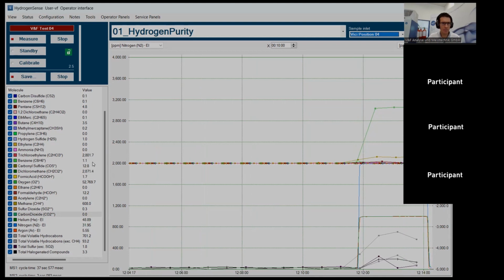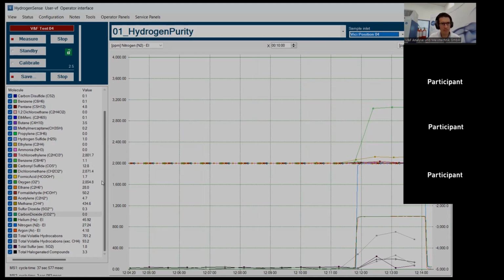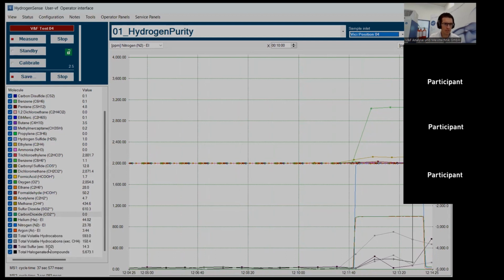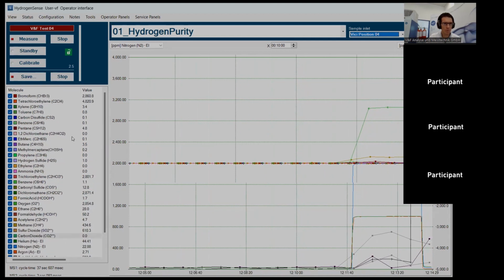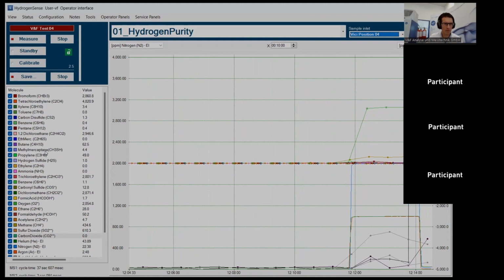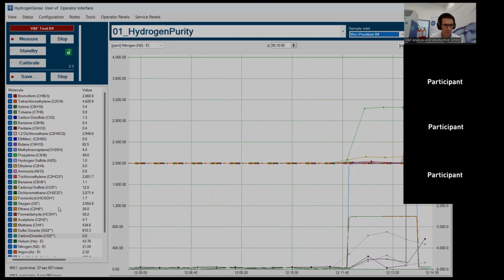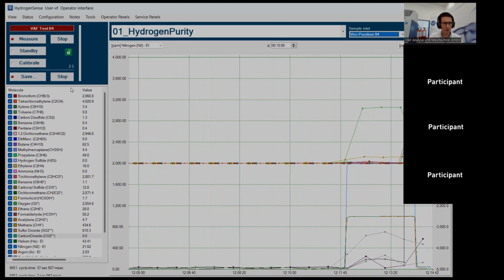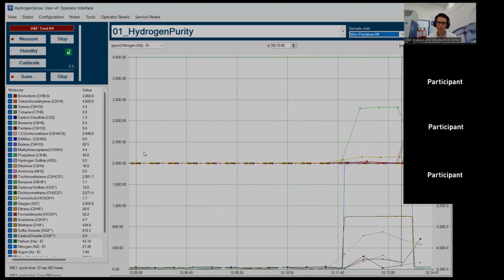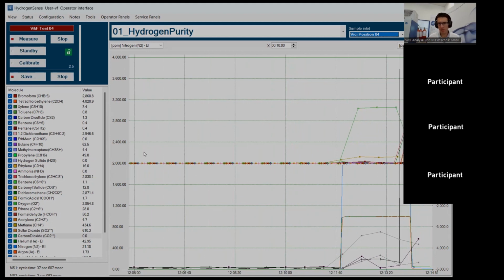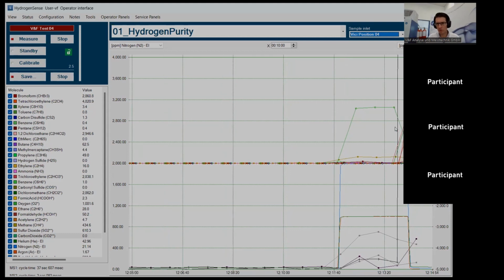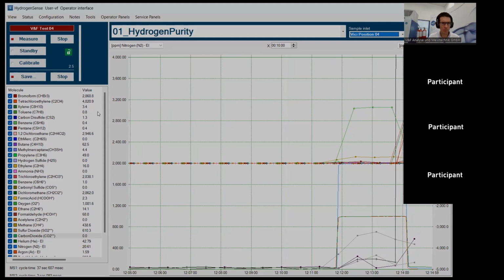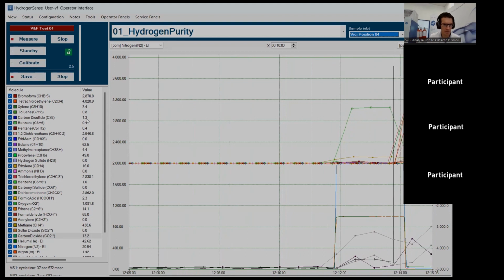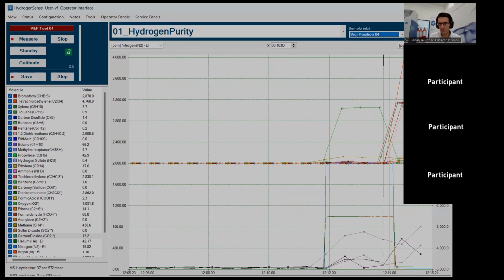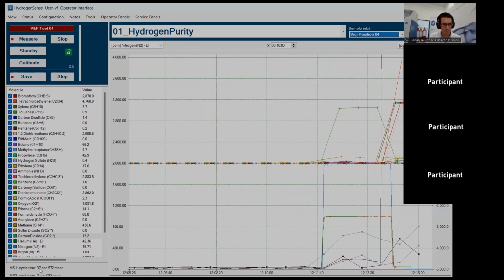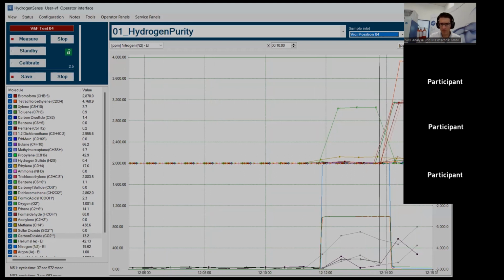And this is a multi-calibration gas bottle which contains the halogenated compounds that we are using to produce the total halogenated signal. So here, for example, we have tribromomethane, tetrachloroethylene, dichloroethane, trichloroethylene, and dichloromethane. All of these are in this calibration gas bottle. Once we give it a few cycles, we will see that upon switching the gas, we are pretty much already getting very close to the nominal concentration in this bottle, which is either 3,000 ppb or 5,000 ppb. And you see here that the distance for each of these data points will always be the cycle time. So here, a new line of points will be produced within 37.5 seconds.